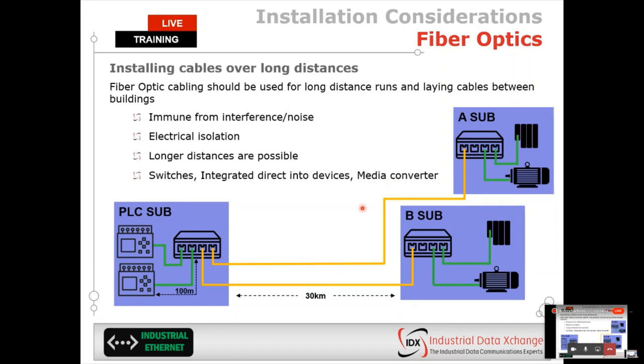But what's also really nice is if I wanted to use managed switches, I could even create a redundant ring. So if I lost either of these fiber cables to each of my substations, I would still have another path to communicate. I would need to use managed infrastructure, and it would need to be configured so that it knows this is a redundant link, and must disable this link unless I lose one of my main fiber connections.